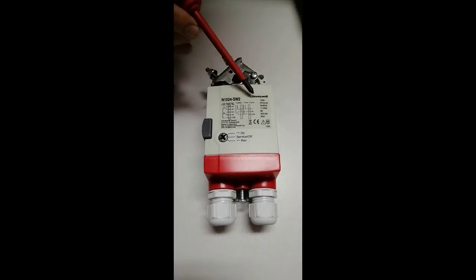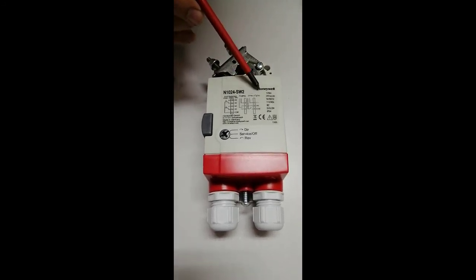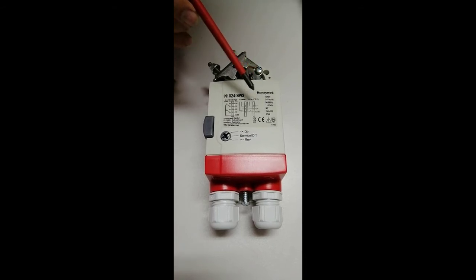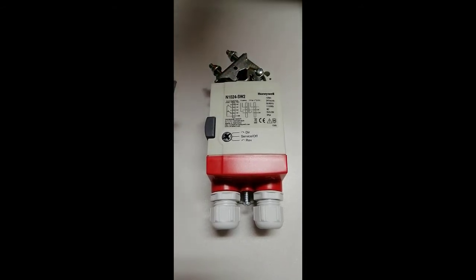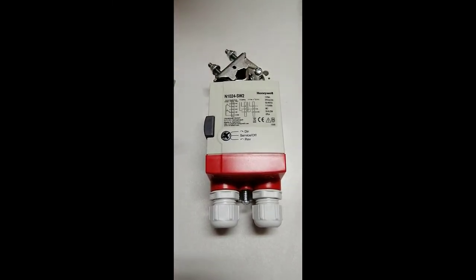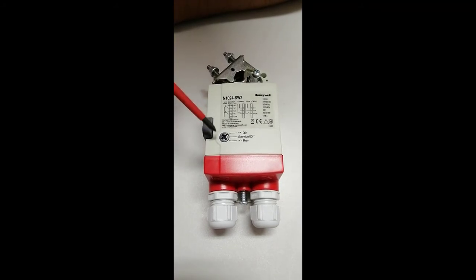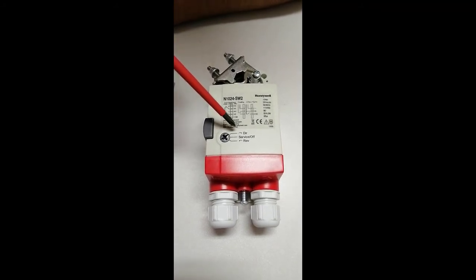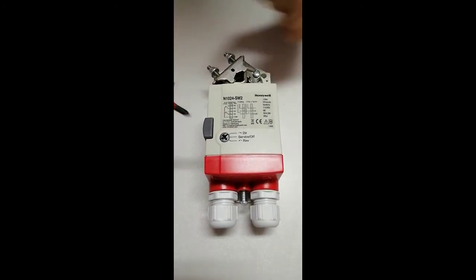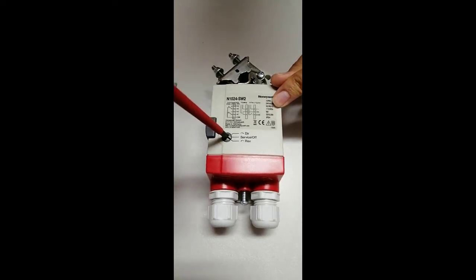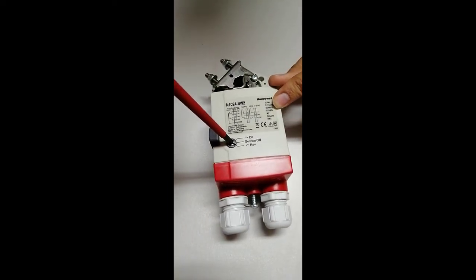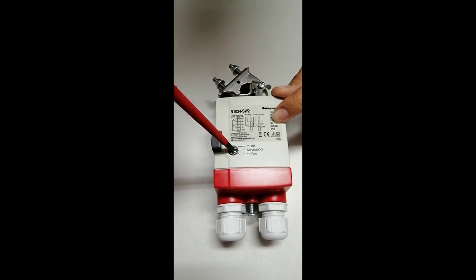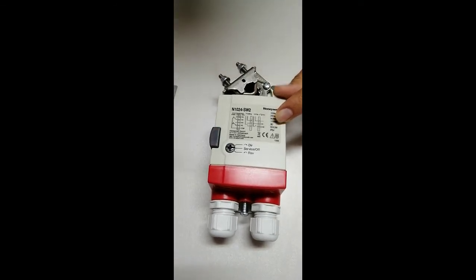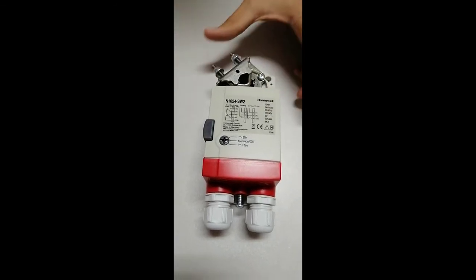We mostly use this two position connection, and we need a 24 volt power supply for this damper actuator. Here we also have a knob to select the direction. For example, if we want it to work in direct acting or reverse acting, we can select it from here. In this position it is now in direct acting. Now it will become reverse acting. In this position, it is in off mode.